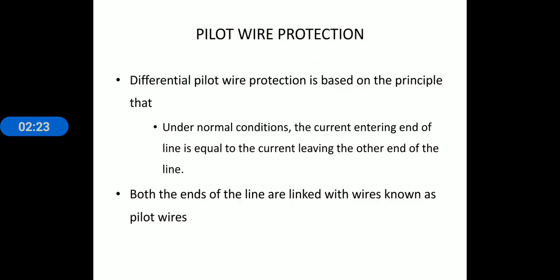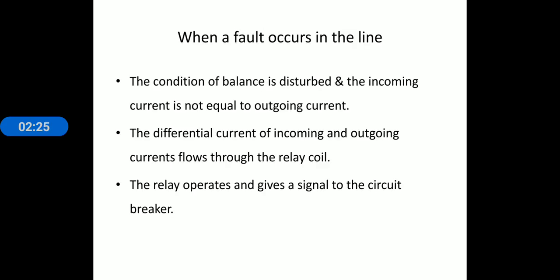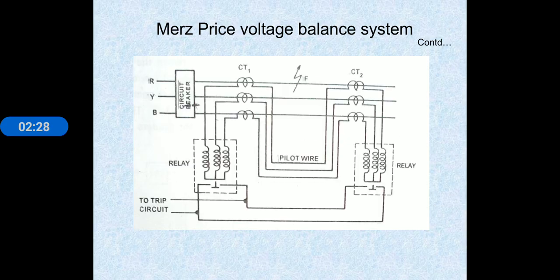Next one, Merz-Price protection, the voltage balance system, also called differential or Merz-Price voltage balance system. See here, it is a schematic diagram for the voltage balance system. Two identical current transformers are connected in each protected line, one at each end of the line. The secondaries of the current transformers are connected to each other, and also to the relay.